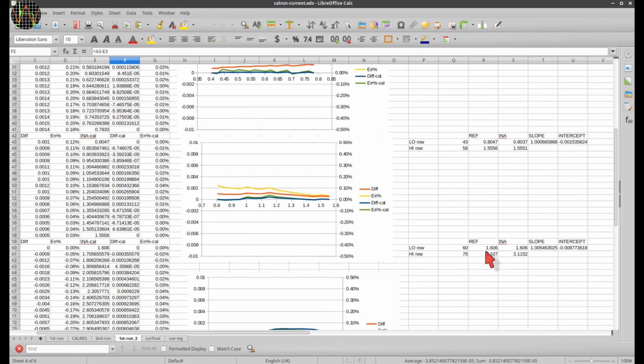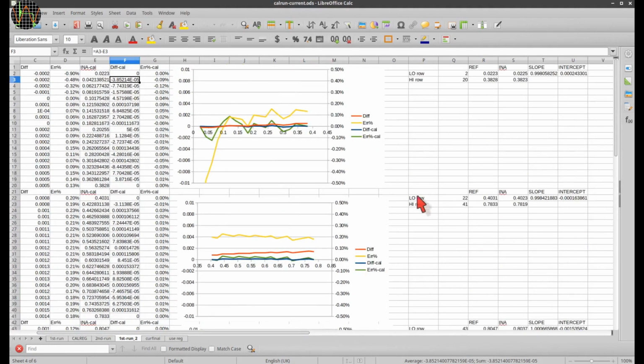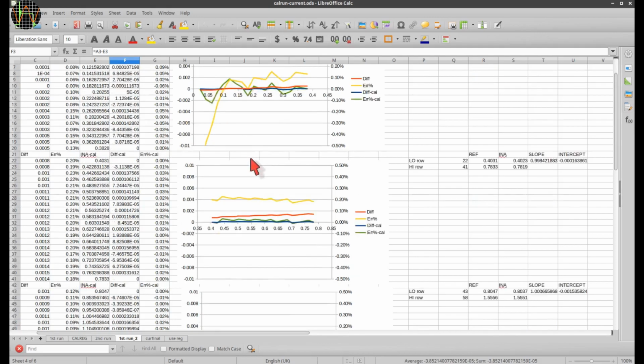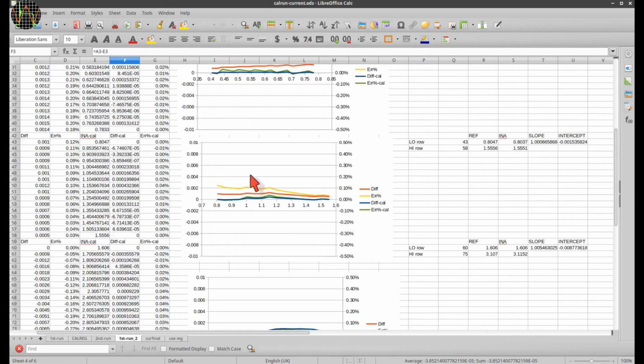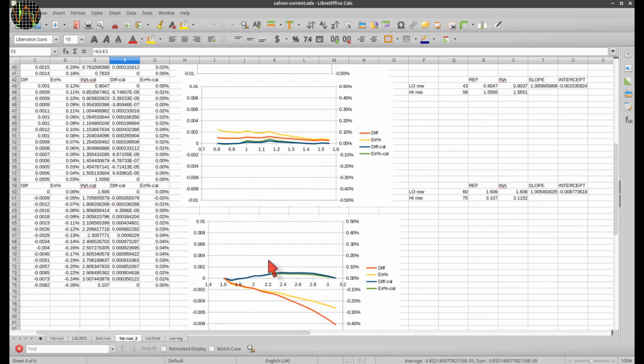I then applied the correction formula to the original data, which you see in column E, calculated the new difference to the original data and the error in percent, and plotted the data together with the previous values. The difference compared to the calreg method is remarkable. This really corrects the error properly. Look just how close the blue and green lines are to 0 compared to the original values.